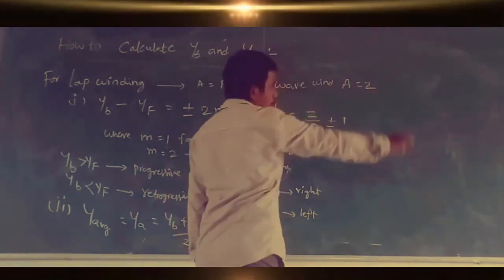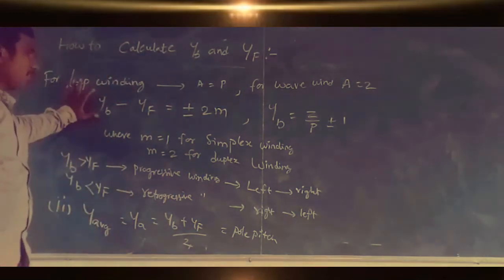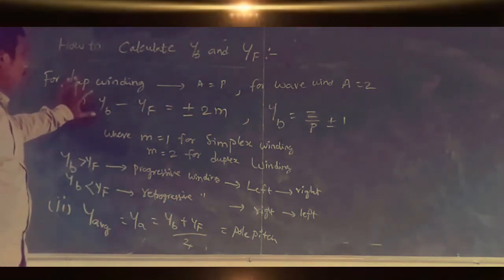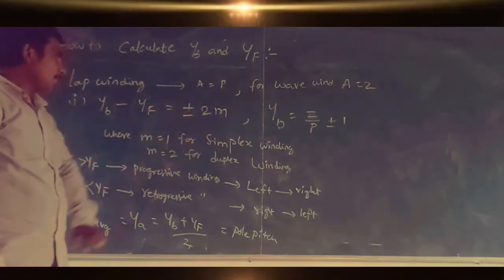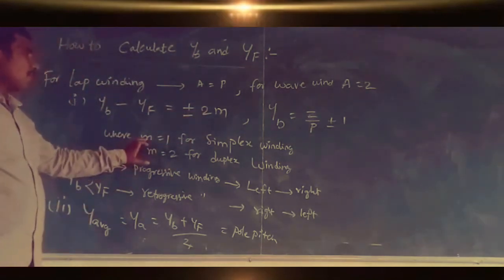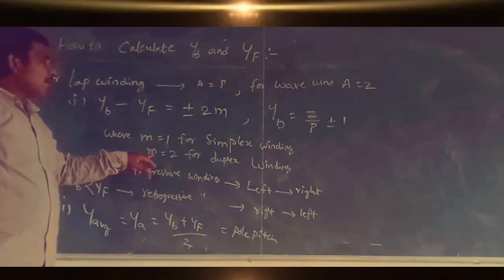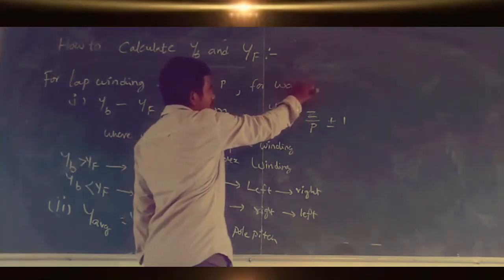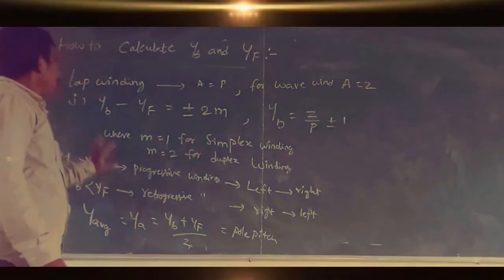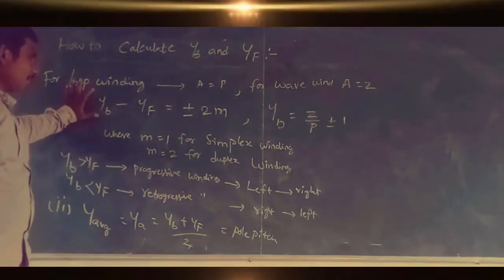For wave winding, the number of parallel paths equals 2. Now, how to calculate back pitch and front pitch: the formula is YB minus YF equals plus or minus 2M, where M equals 1 for simplex winding. Plus is for progressive winding and minus is for retrogressive winding.